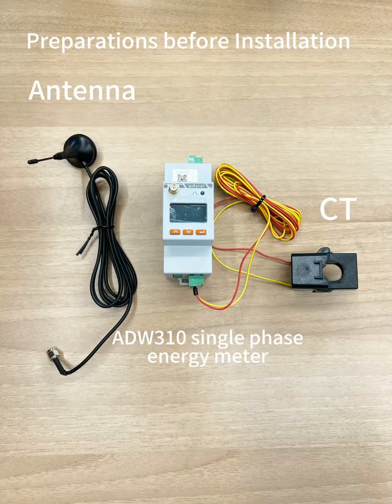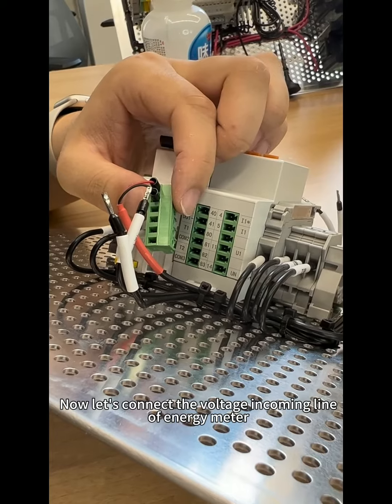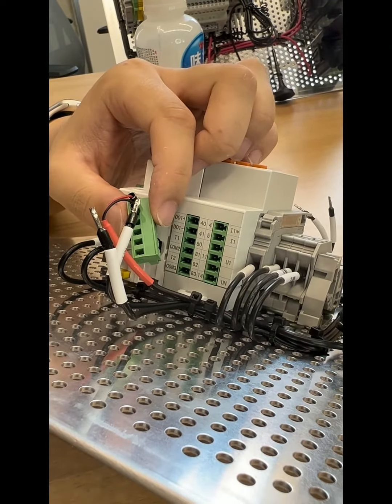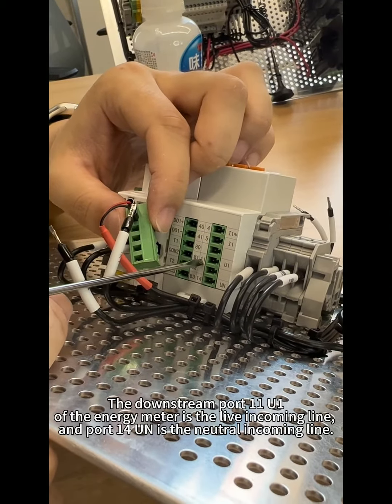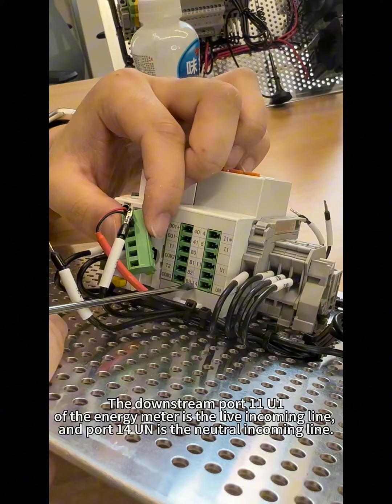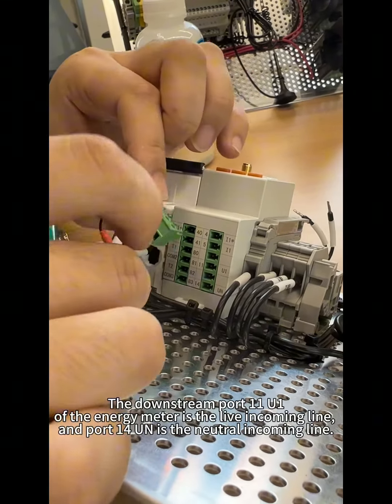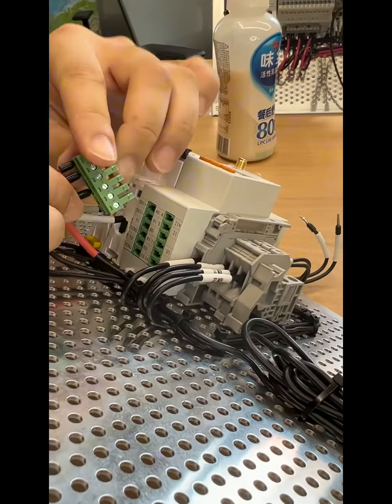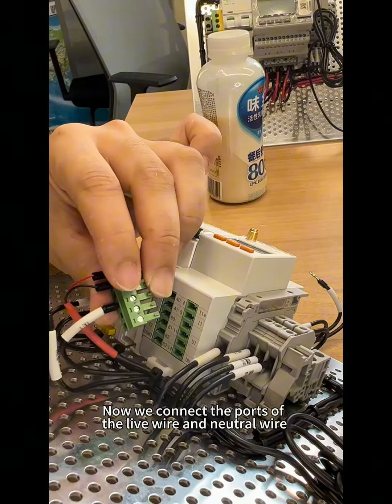Preparations before installation. Now let's connect the voltage incoming line of the energy meter. The downstream port 11 U1 of the energy meter is the live incoming line, and port 14 UN is the neutral incoming line. Now we connect the ports of the live wire and neutral wire.